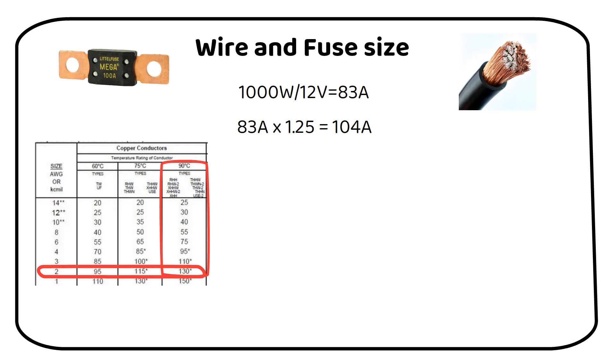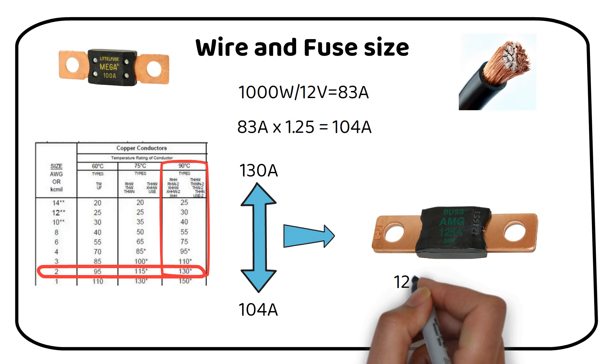For fuse selection, we aim for a capacity between the system's current requirement of 104 amps and the wire's maximum capacity of 130 amps. A 125 amp mega fuse is ideal for our setup.